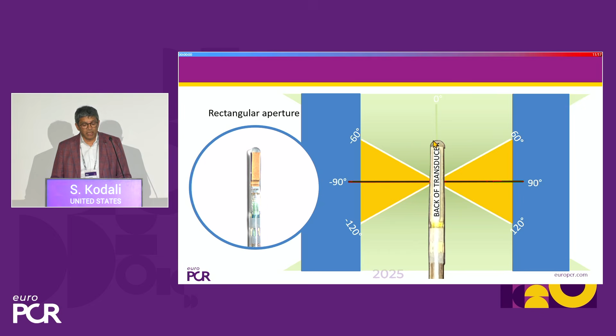So when you're using the probe, you have to keep that in mind. At 0 degrees is obviously the largest aperture, and you have the best quality imaging. But as you get closer to 90, that goes off. And so that becomes relevant when you're using X-plane.